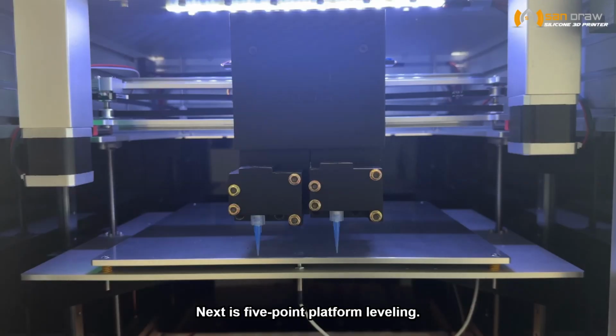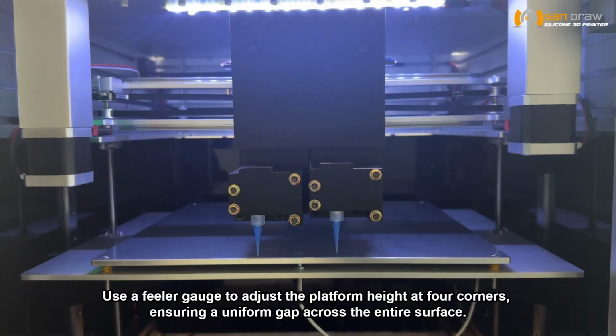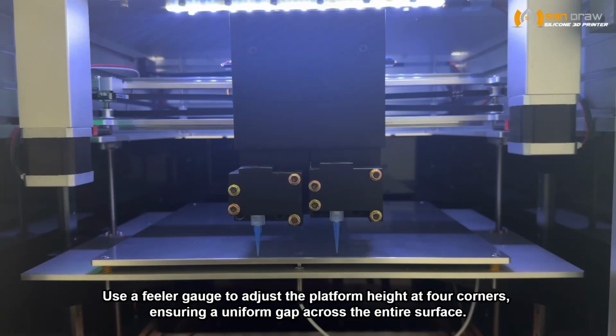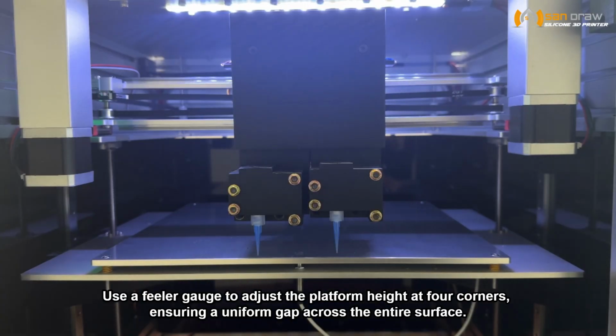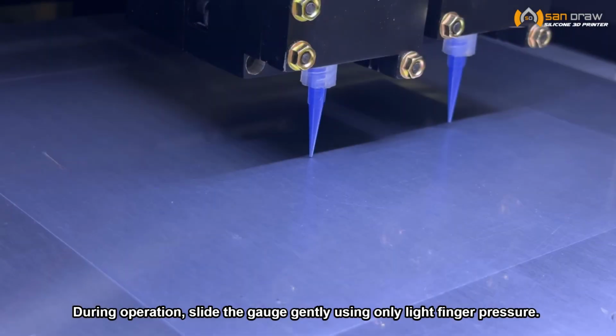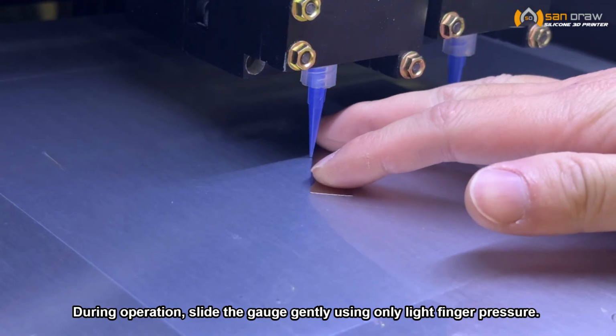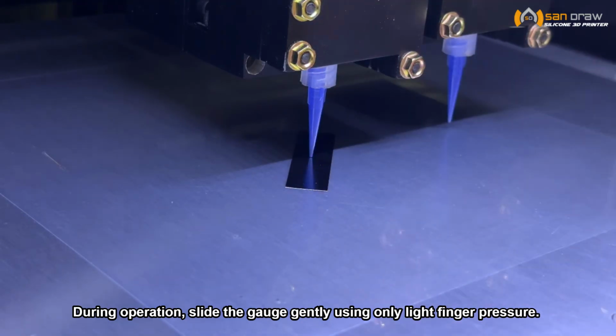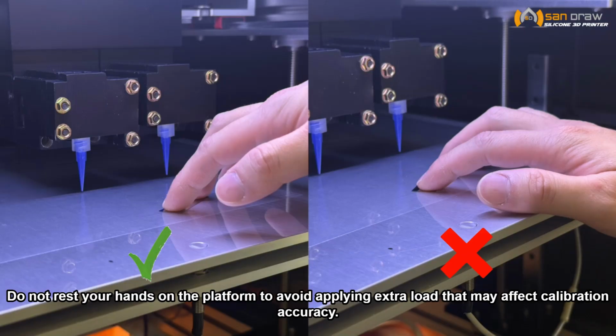Next is 5-point platform leveling. Use a feeler gauge to adjust the platform height at 4 corners, ensuring a uniform gap across the entire surface. During operation, slide the gauge gently using only light finger pressure. Do not force it in. Do not rest your hands on the platform to avoid applying extra load that may affect calibration accuracy.